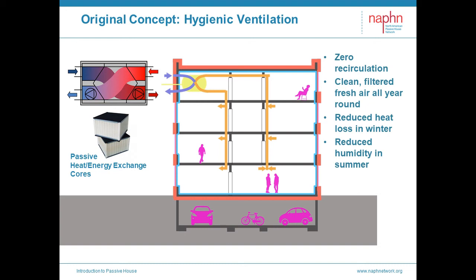Typical buildings have ventilation systems — just typically bad ones — often providing only intermittent exhaust from bathrooms and kitchens that don't ensure good ventilation everywhere. In commercial buildings, the ventilation system often includes a lot of recirculated air. In a passive house building, we supply 100% fresh air to every served space — the bedrooms, living rooms, offices, classrooms — and 100% exhaust from every service area — the bathrooms, kitchens, and utility areas — operating continuously, 24/7. The systems are laid out to ensure that all spaces have robust ventilation, with zero recirculation.